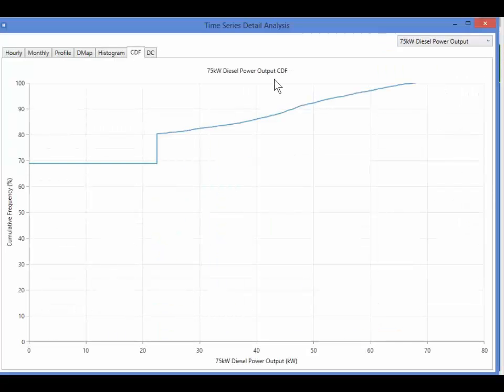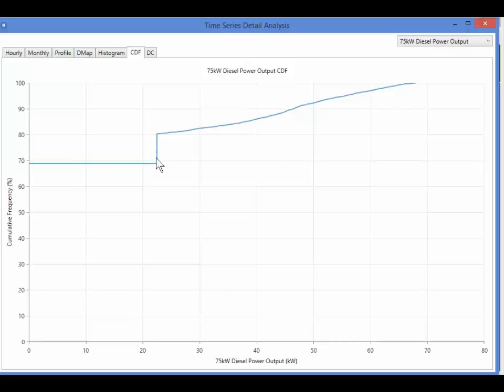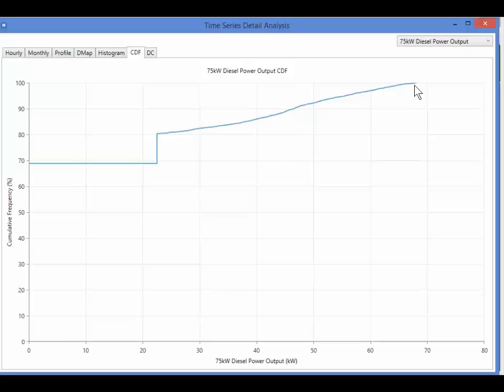CDF stands for Cumulative Distribution Function, and gives similar info. For example, here I can see that the 75 kilowatt diesel spends almost 70% of its time turned off, and never operates below its minimum load, since Homer won't allow that. Another 11% or so of its time is spent at minimum load, for a total of about 80%. The output is around 68 kilowatts or less 100% of the time, which means that it never exceeds 68 kilowatts output.